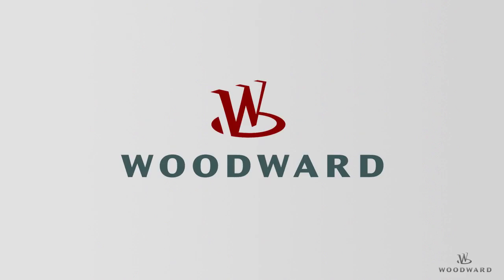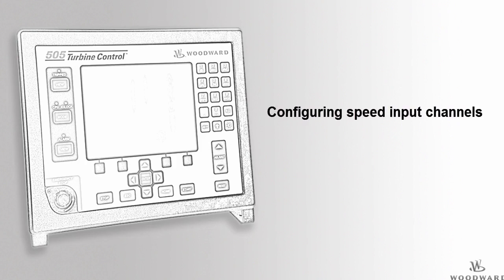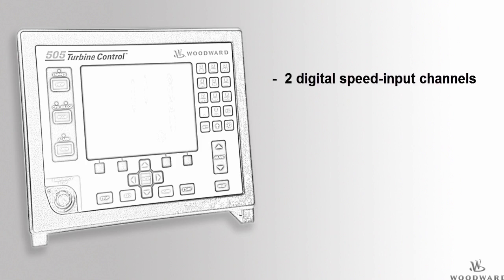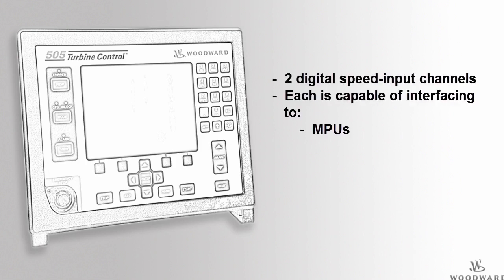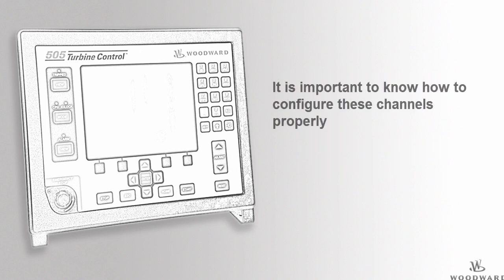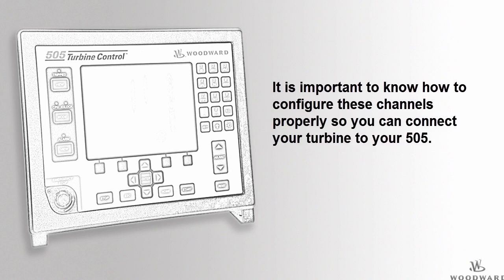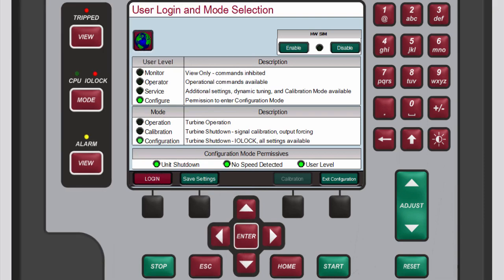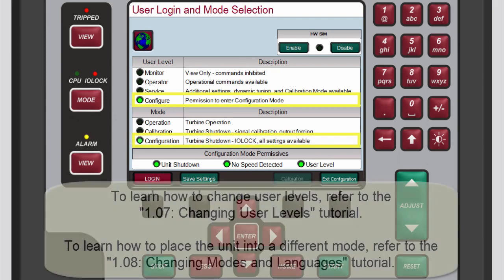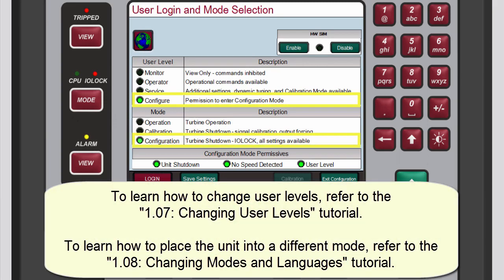Hello, and welcome to the 505 tutorial for configuring speed signals. In this tutorial, you will learn how to configure speed input channels. The 505 has two digital speed input channels capable of interfacing to magnetic pickup units, or MPUs, and proximity speed probe sensors. It is important to know how to configure these channels properly to connect your turbine to your 505 controller. To configure speed input channels, you must be logged in to the Configure User Level and Configuration Mode. Refer to the Changing User Levels and Changing Modes and Languages tutorials to learn how to do this.